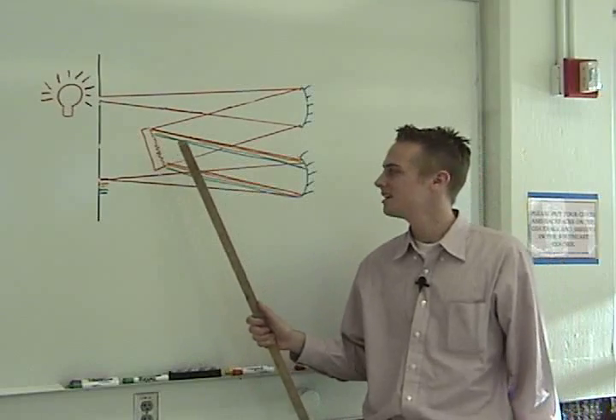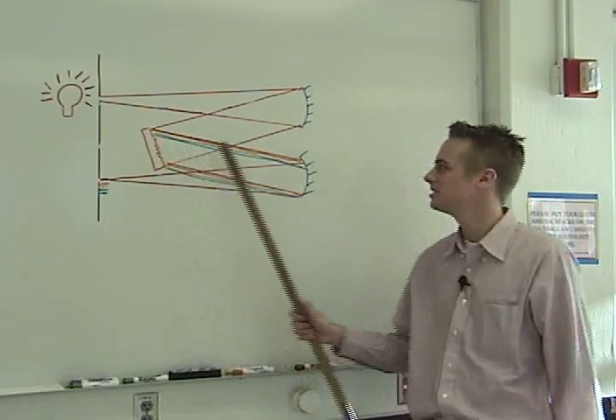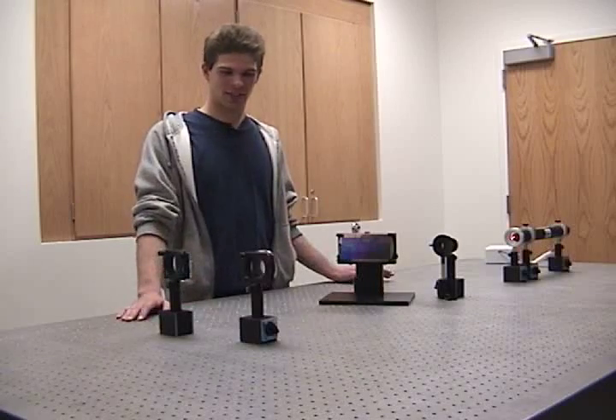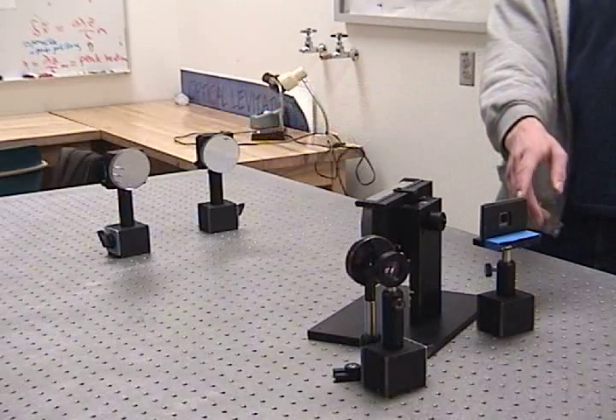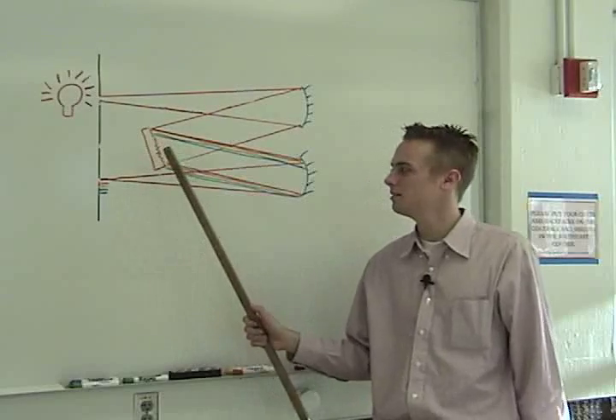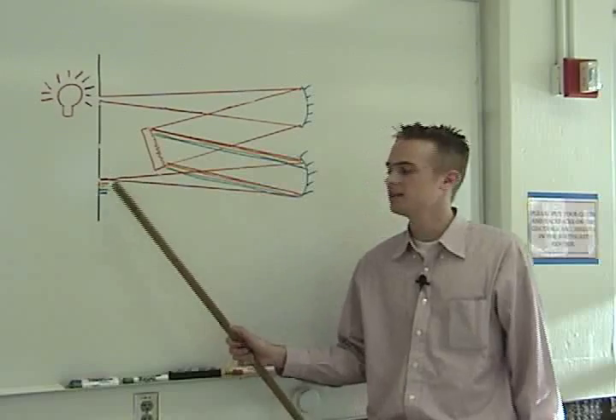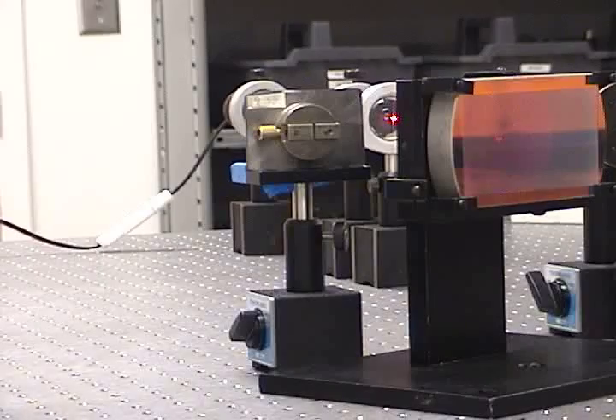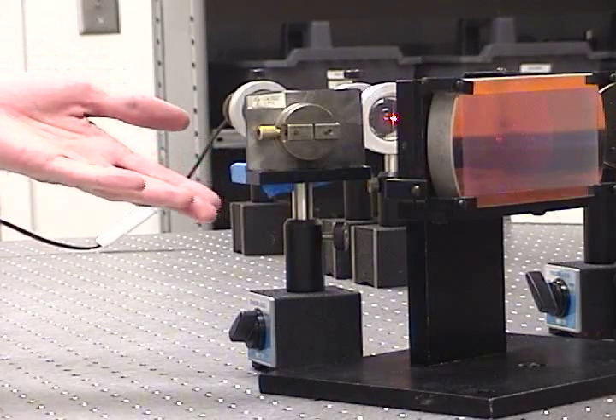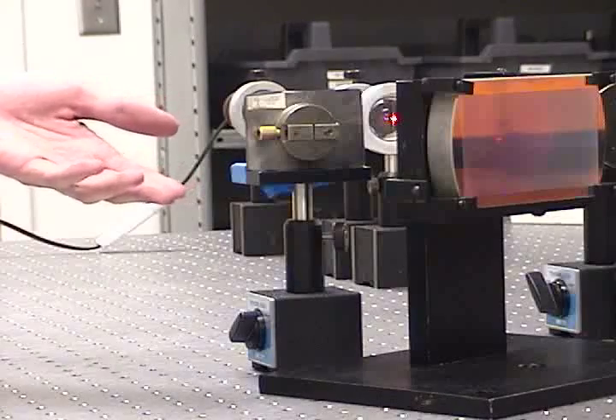Different wavelengths are diffracted at different angles. The second mirror will send the diffracted light to the second aperture. Depending on the angle of the grating, different wavelengths will be aligned at the aperture. At the aperture we get the Fraunhofer pattern diffracted from the grating.